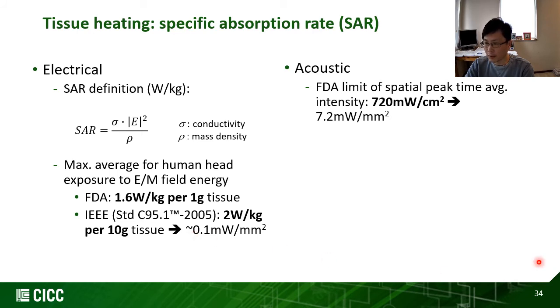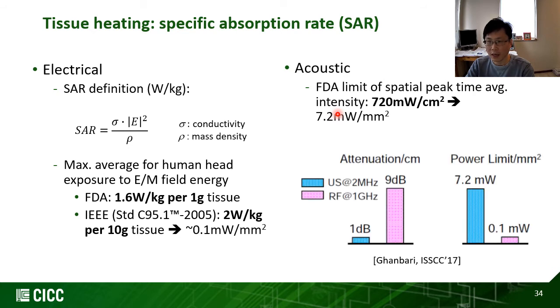For the acoustic one, it is also well known in many ultrasound applications. The limit is the spatial peak time average intensity limit of 720 milliwatts per square centimeter, which can be translated to 7.2 milliwatts per square millimeter. If we compare the electrical and acoustic, we can see the SAR regulation limits the maximum amount of power that can propagate inside the tissue. The acoustic apparently allows much higher power inside the tissue, which has a low chance of causing tissue heating.